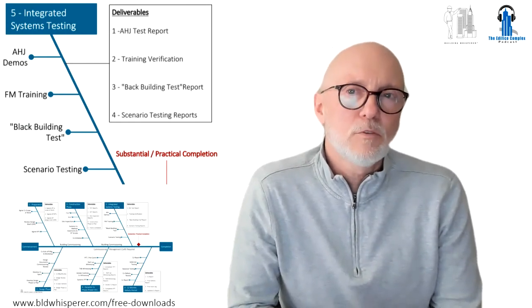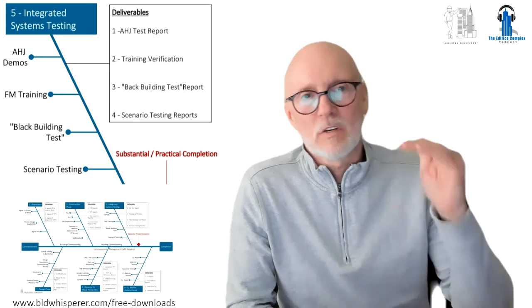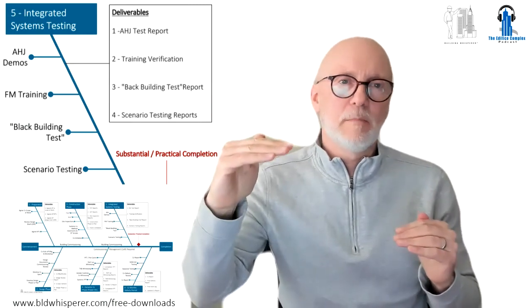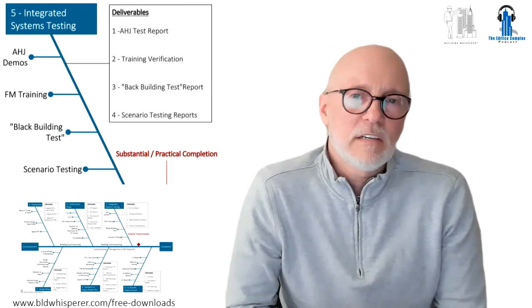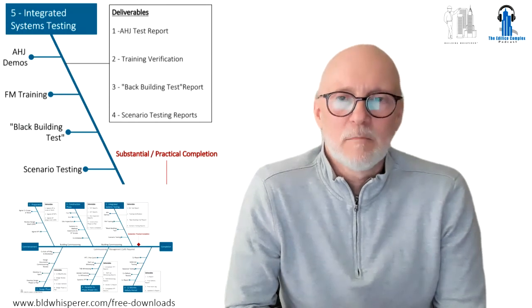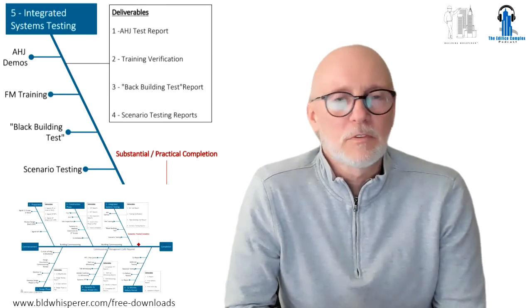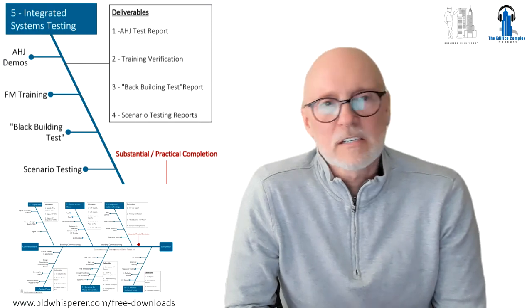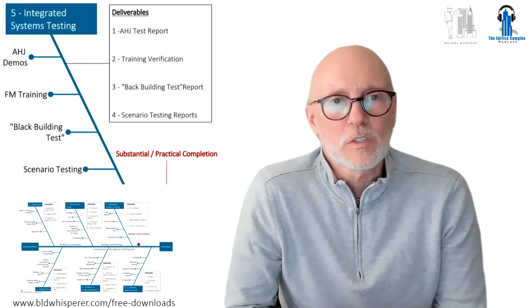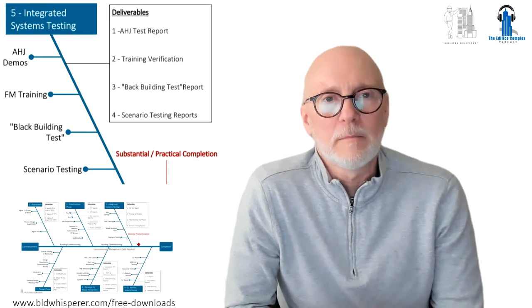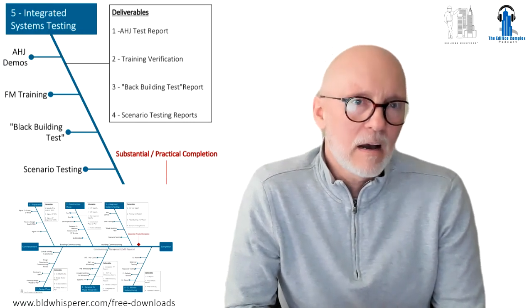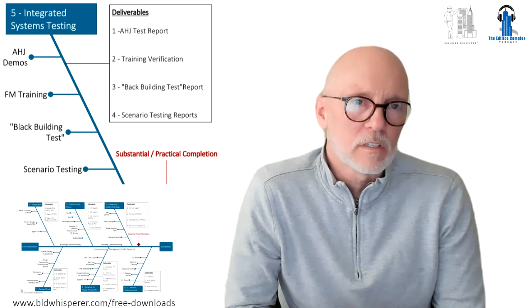So we need to close this gap between reality and what people think they're buying. IST really is, in my mind, a risk management thing. If I'm an owner with a data center and I want 99.99% uptime, I have to test all possible single points of failure, all possible failure modes, and the resilience and comeback from any failures or disasters.